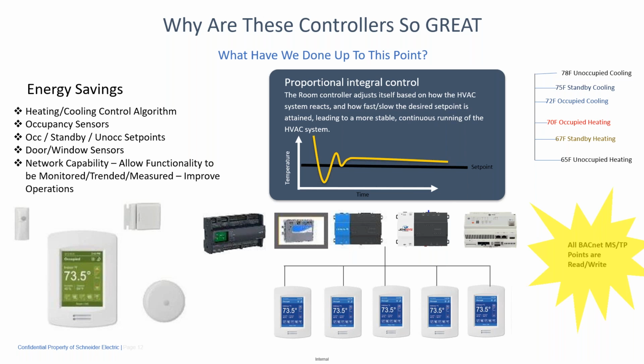The PI controller in each one of them operates over time, so the longer it gets to work, the closer it hones in on the set point. And so you can be assured of that control. The same PID loop has been used in our 7000 series controllers as the 8000 series controllers. So you have that capability over time to be able to get closer to set point as time goes on.